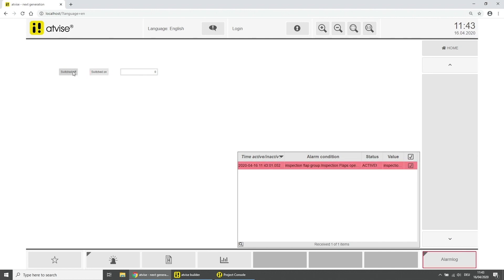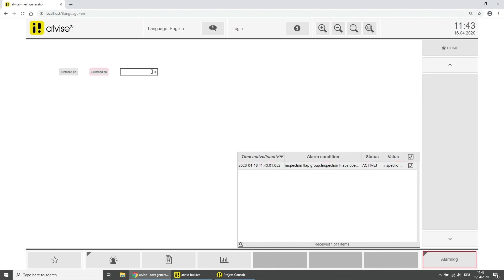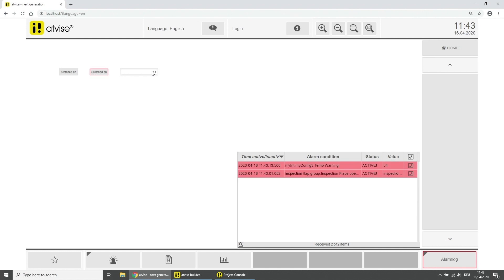Click on the first button. Because of the group with all conditions of the boolean data variables, no new alarm is triggered. Only the sum alarm is visible in the alarm list. Enter a value above 50 into the in-out value element. The alarm appears without a delay in the alarm list. Hide the alarm list by clicking on Alarmlog.